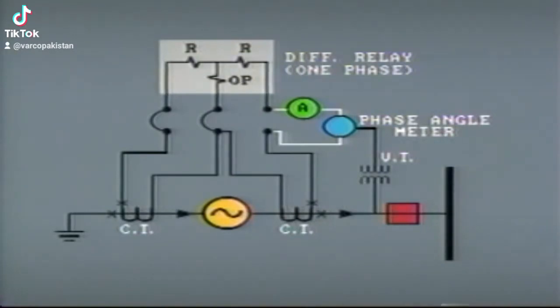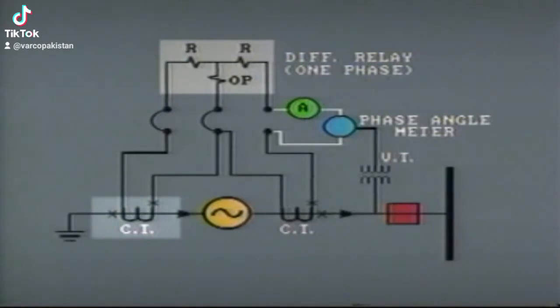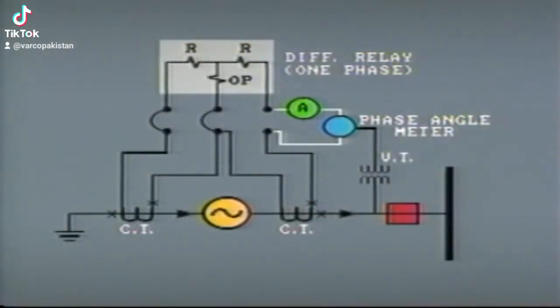If the test shows different phase angle relationships, then the CTs have been incorrectly connected. However, this problem should have been discovered earlier by secondary or primary injection tests. Transformer differential protection can be measured in a similar manner.